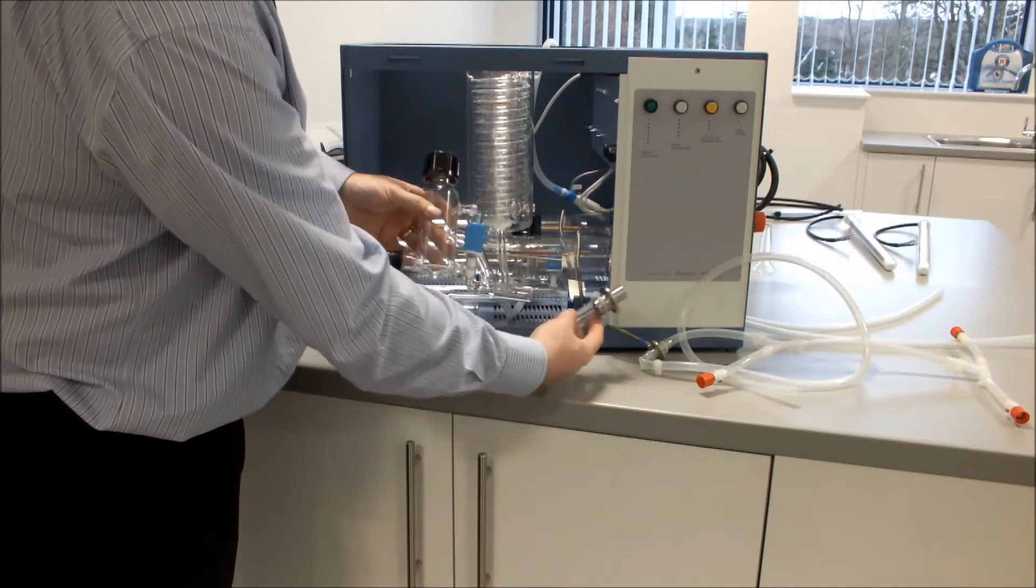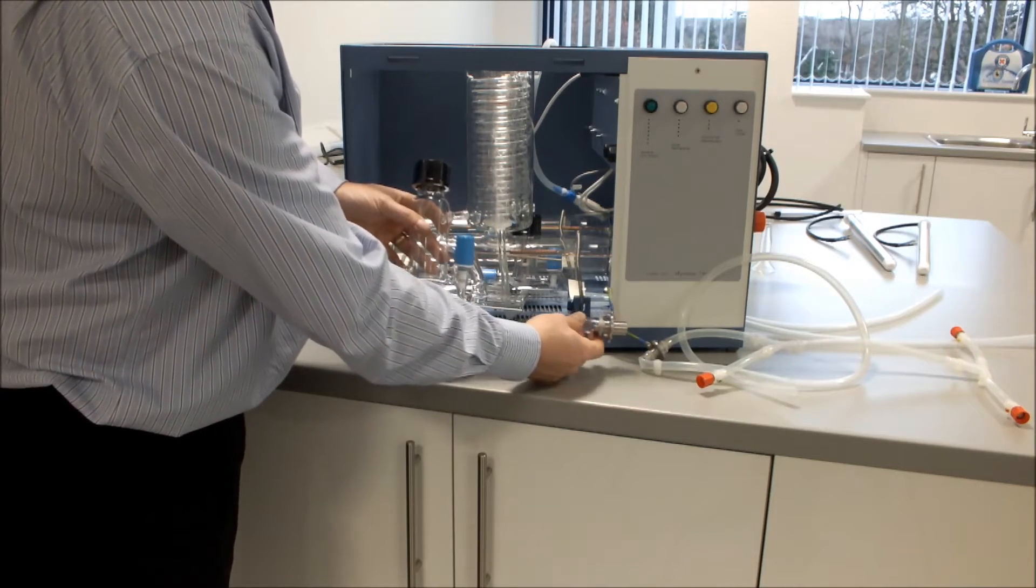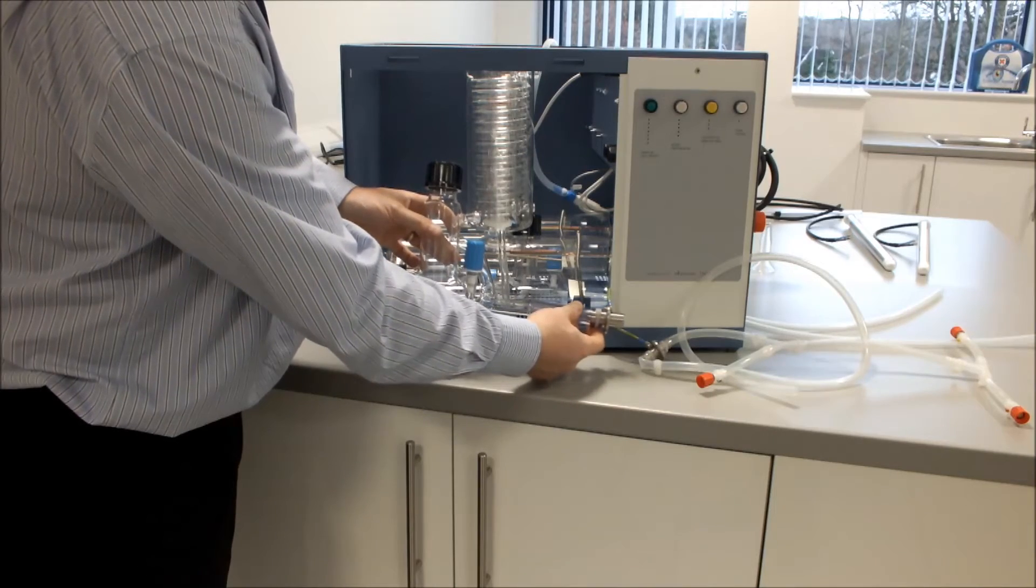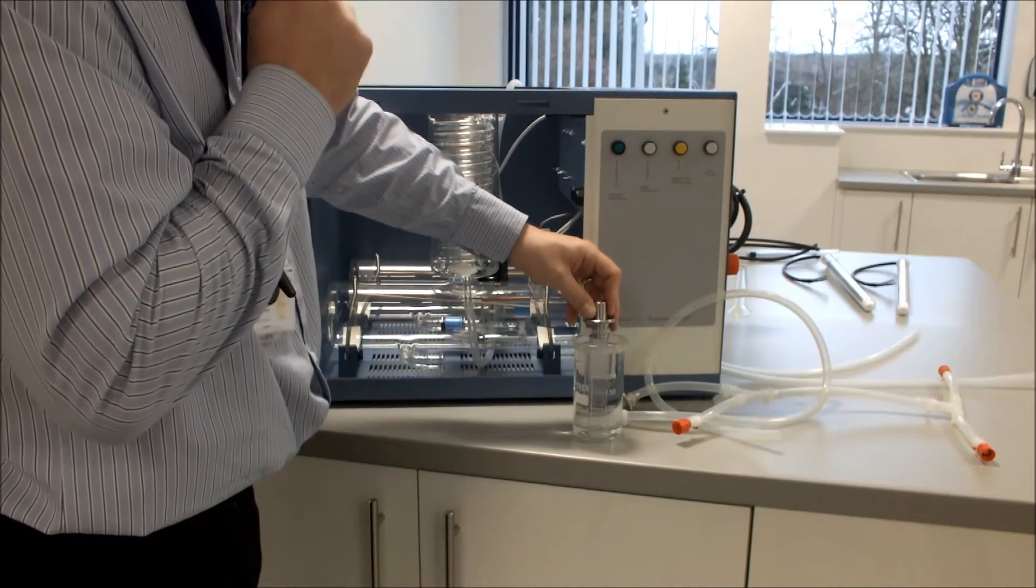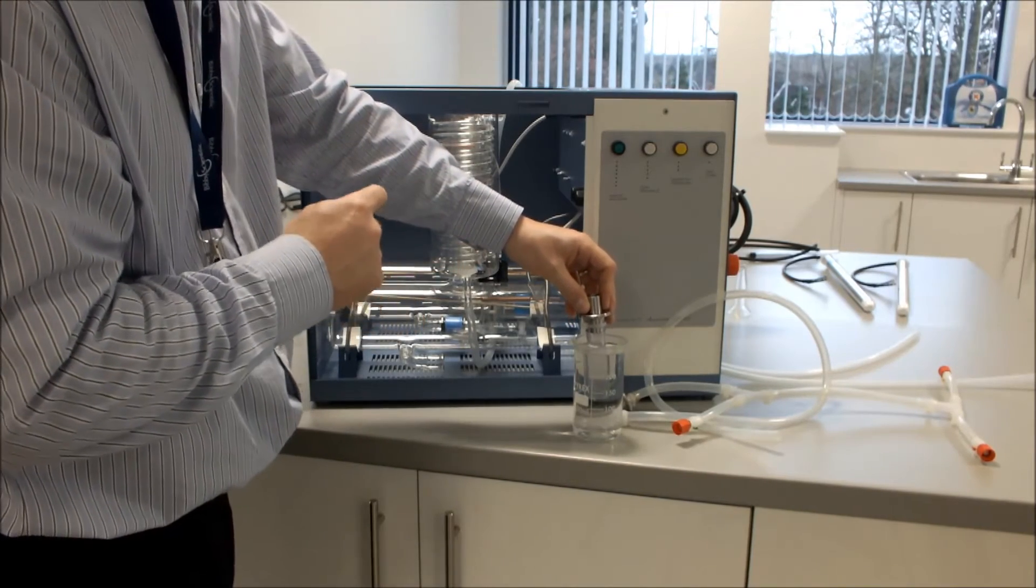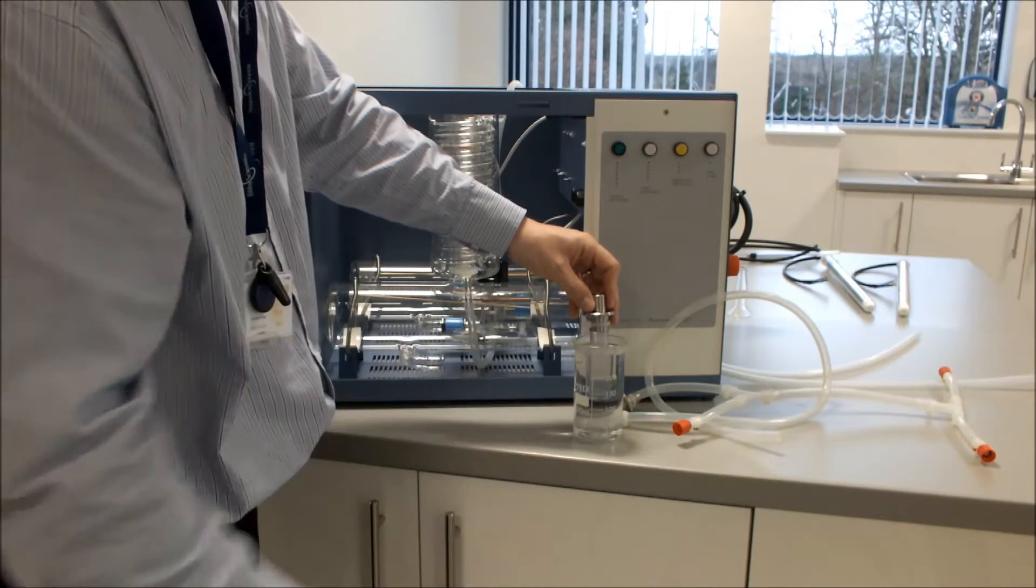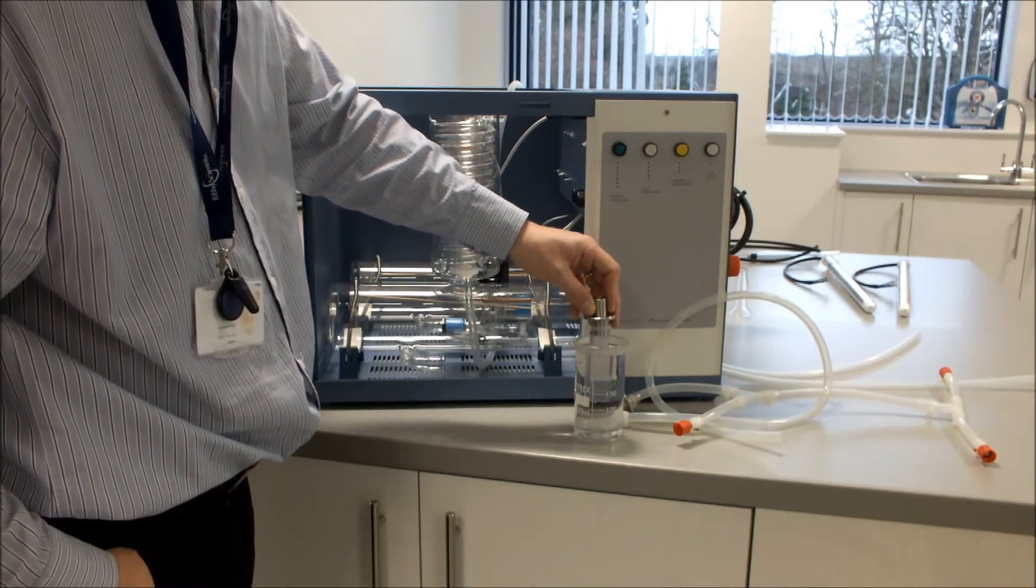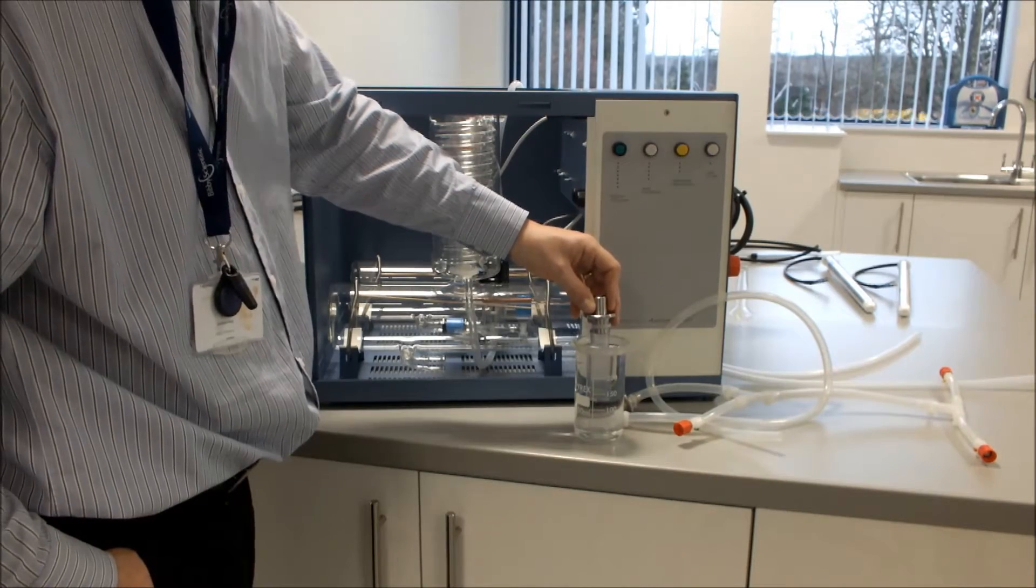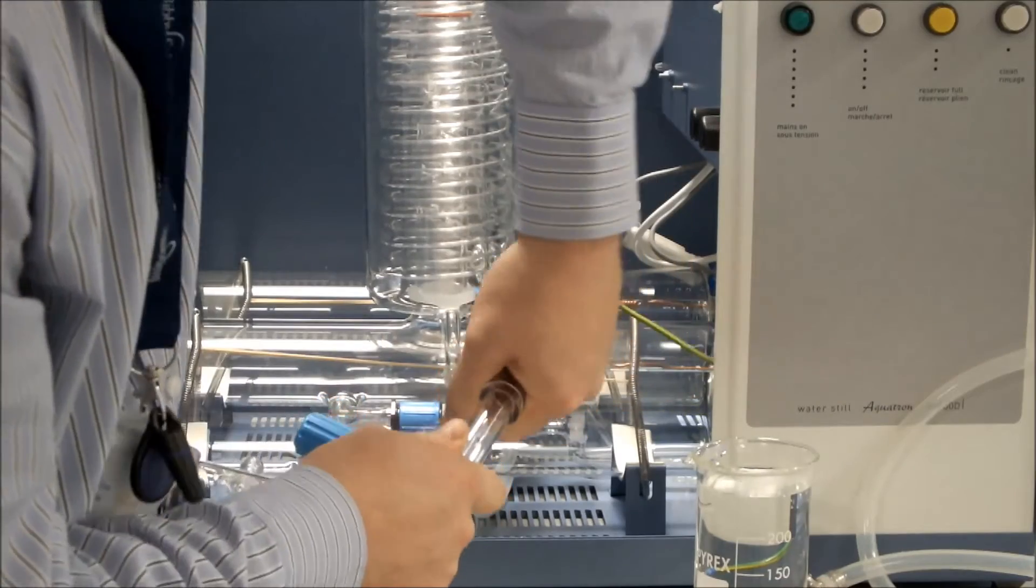We will then connect the drain outlet to our front boiler control. It's easier to immerse the 16mm hose into some hot water for approximately 20 seconds. We then connect the 16mm hose onto the drain of our front boiler control. Again this will be tie wrapped.